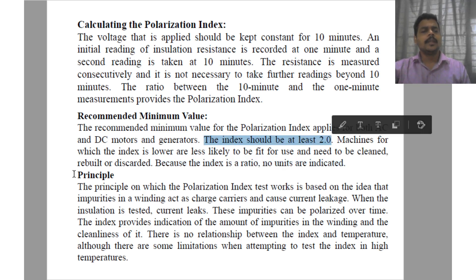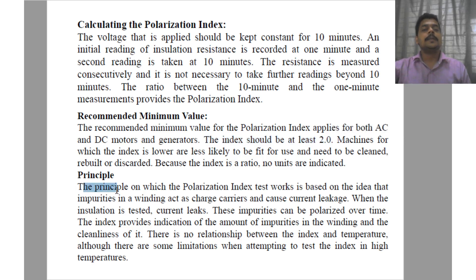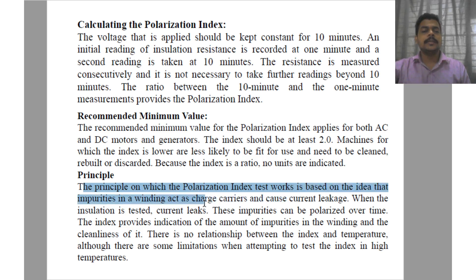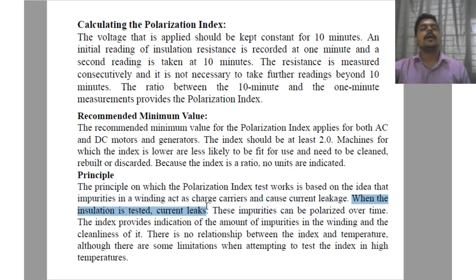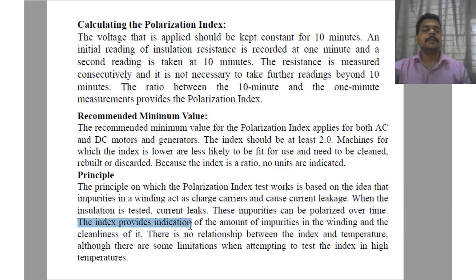The principle on which the polarization index test works is based on the idea that impurities in a winding act as charge carriers and cause current leakage. When the insulation is tested, current leaks through these impurities, which can be polarized over time. The index provides an indication of the amount of impurities in the winding and the cleanliness of it.